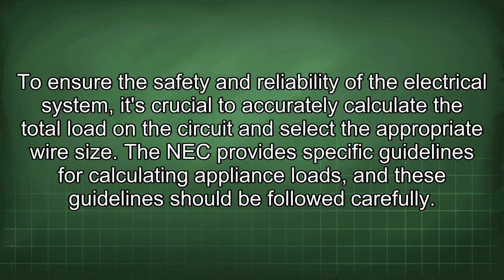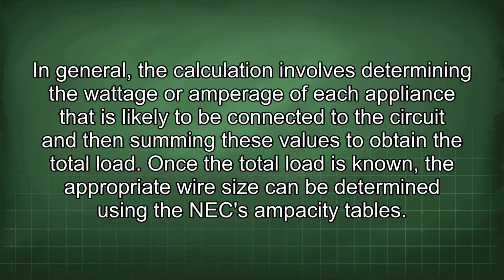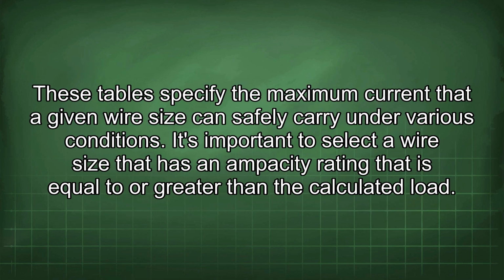To ensure the safety and reliability of the electrical system, it's crucial to accurately calculate the total load on the circuit and select the appropriate wire size. The NEC provides specific guidelines for calculating appliance loads, and these guidelines should be followed carefully. In general, the calculation involves determining the wattage or amperage of each appliance that is likely to be connected to the circuit and then summing these values to obtain the total load. Once the total load is known, the appropriate wire size can be determined using the NEC ampacity tables. These tables specify the maximum current that a given wire size can safely carry under various conditions.